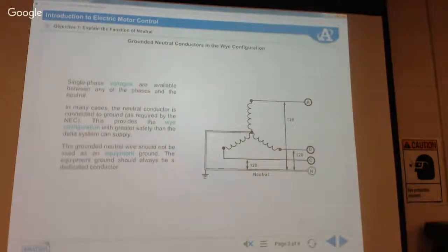And notice there is a grounding right here. I don't really like that. That grounding diagram, this little symbol here, in my opinion, should be back here. Kind of confusing. There shouldn't be an earth ground before we get back to our neutral distribution. Typically, you'll see them tied at the same place right here, but not out there in the field. Because what we want is we want everything to come back here, close to the transformer, and go to ground.